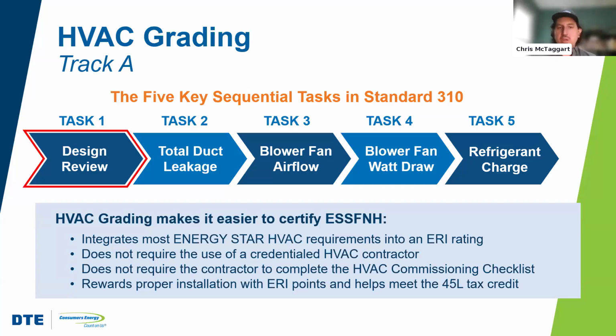Then the rater is able to perform total duct leakage testing, and a minimum level of duct tightness is required, followed by blower fan airflow testing, basically to make sure that we're moving enough air from our HVAC system that will help to heat and cool people. And then we'll do a blower fan watt draw. It's important to note that's actually an optional test for Energy Star. You don't have to do a blower fan watt draw if the rater either doesn't have the appropriate equipment or they're not licensed to do that type of test. But I personally think it adds a lot of value. And then finally, a refrigerant charge review, either the non-invasive method or the weigh-in method would be allowed.